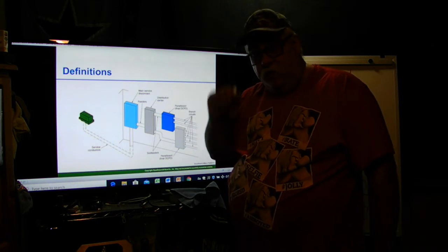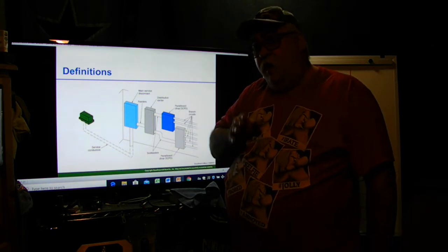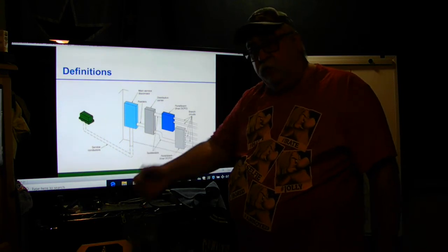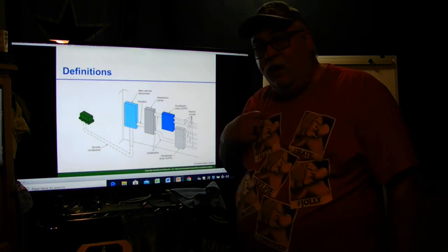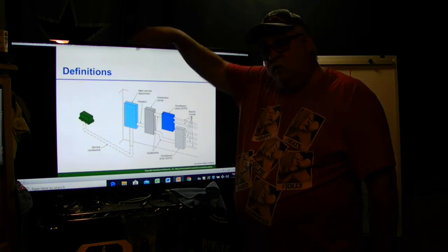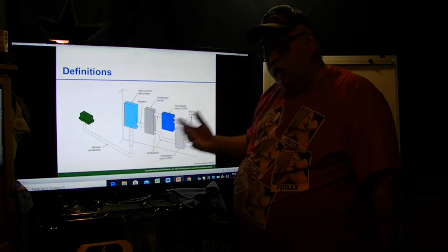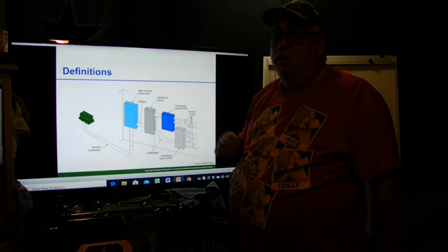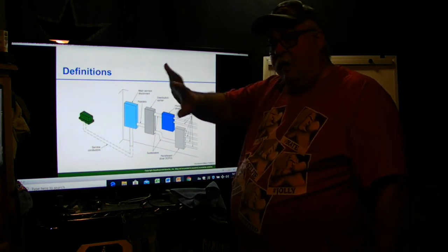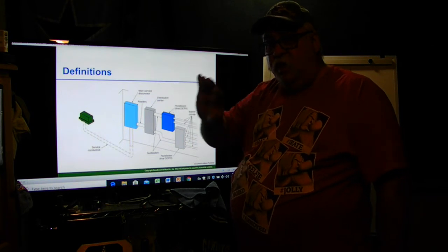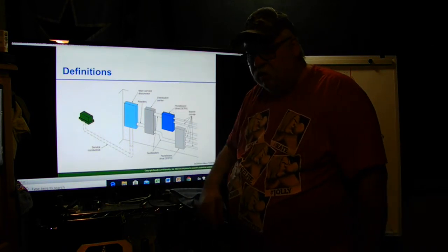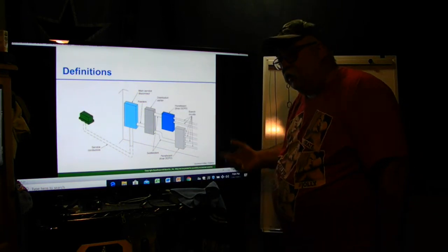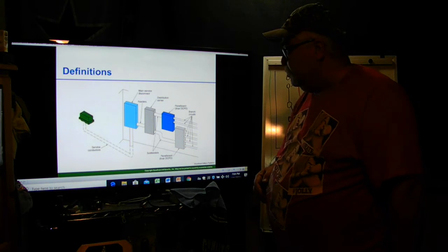So we have a subfeeder. We have a feeder that goes to panel HA, and then from that HA it goes out to the transformer, and from the transformer it comes back into panel LA. I'm talking about the two panels in the front of the classroom, and that's how that's fed. And then all our lighting, all our motors, come out of the HA. Our power, our receptacles, all come out of LA, which is low voltage. The other one is HA, high voltage.